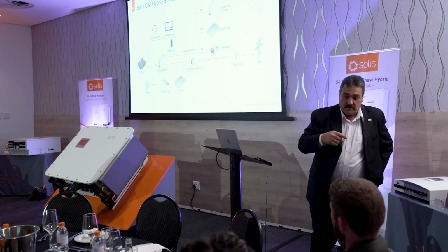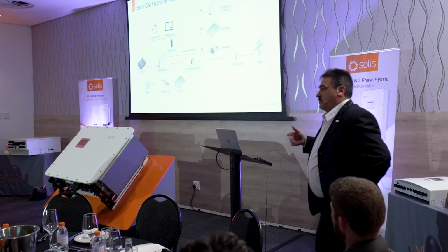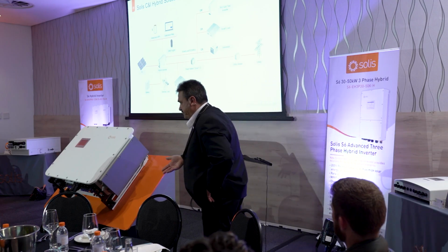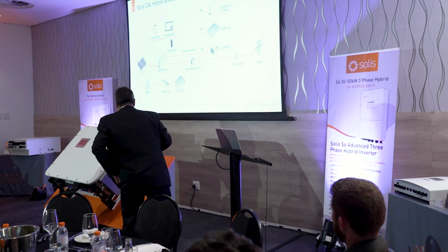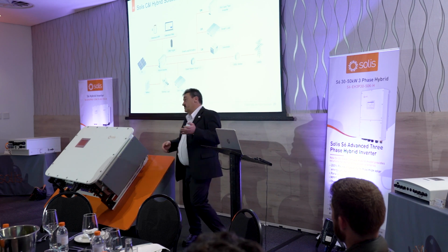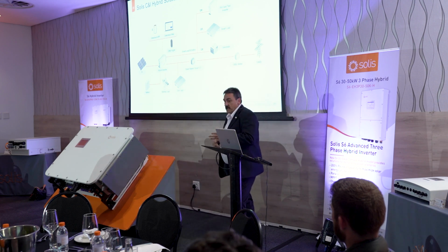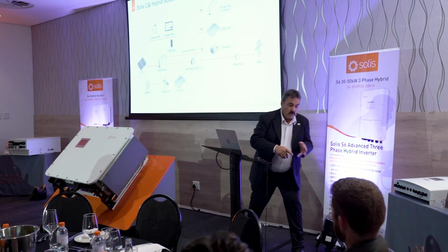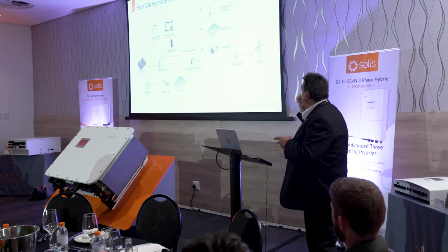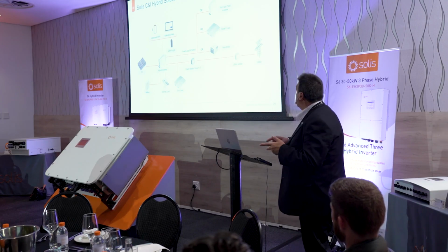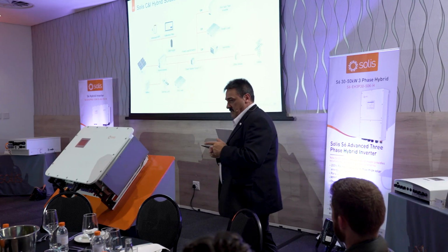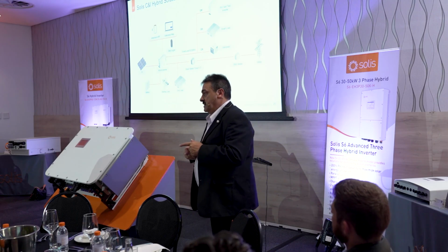So what do we mean by that? The inverter is equipped with what we call a smart port. That smart port has 3 functions. One, you can connect a generator to it. Two, you can put a smart load on it, which I'll explain in a minute. And three, you can AC couple a PV grid-tie inverter to it.